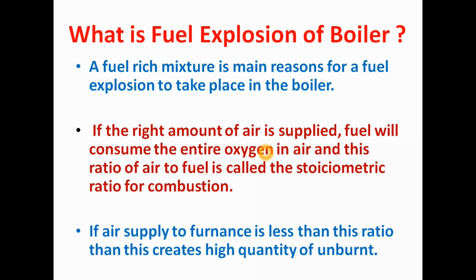The main reason for fuel explosion in a boiler is the fuel-rich environment generated in the furnace. So how does this fuel-rich environment get generated? For combustion of any fuel, we require air or oxygen for its complete combustion. If in the boiler furnace we do not supply enough oxygen or air for complete combustion of the fuel, then some fuel remains in an unburned condition in the furnace, and it goes on accumulating in the furnace.